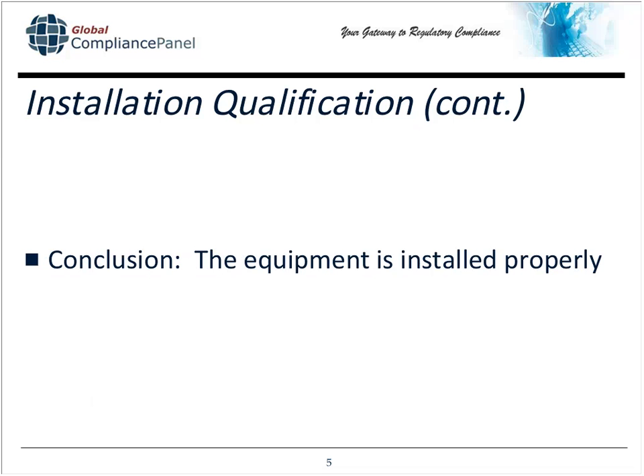The departments or disciplines or cross-functional areas that you determine need to sign an IQ and OQ and a PQ can be different between the three of those. But you've got to make sure that your standard operating procedure specifies which functions, which areas need to sign the conclusions for each of these. I've been cited by notified bodies specifically when I don't account for this, because if a notified body or other auditor or inspector sees inconsistencies between processes, they're going to ask to see the governing document. And when your governing document is not clear, you will be cited for that from a compliance perspective.